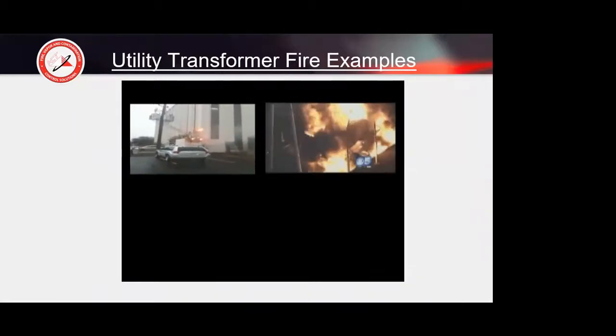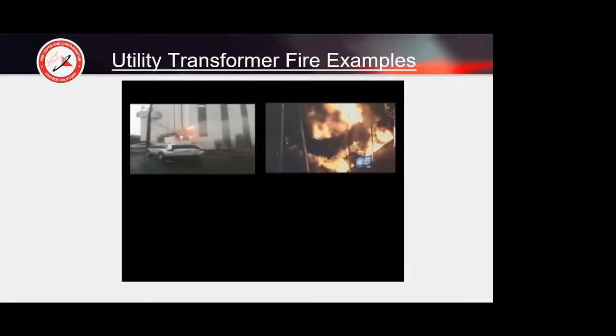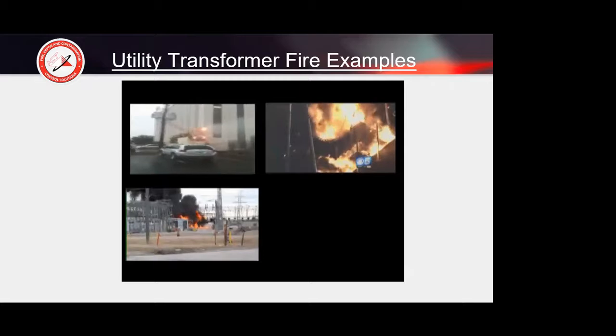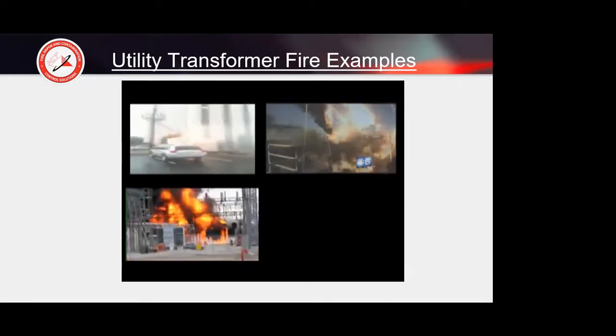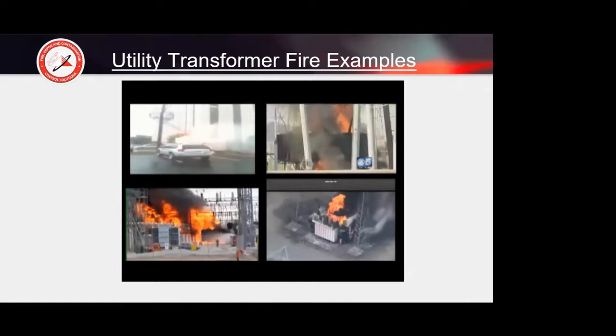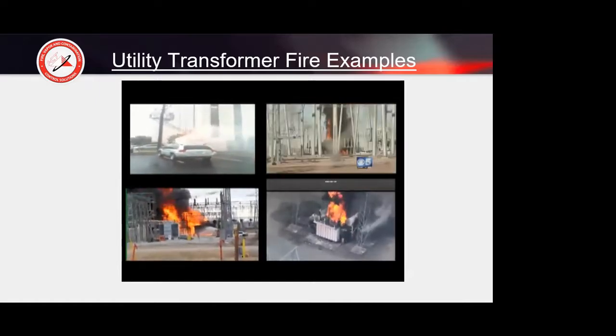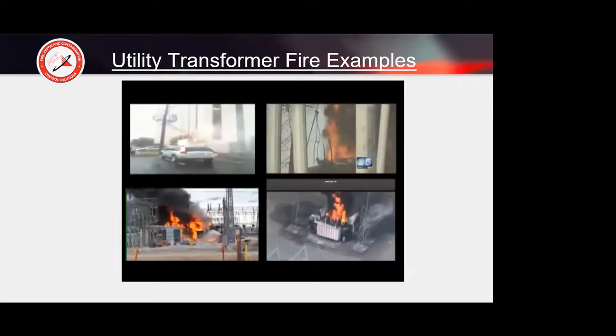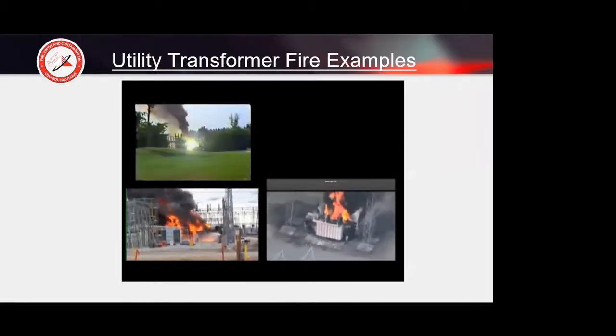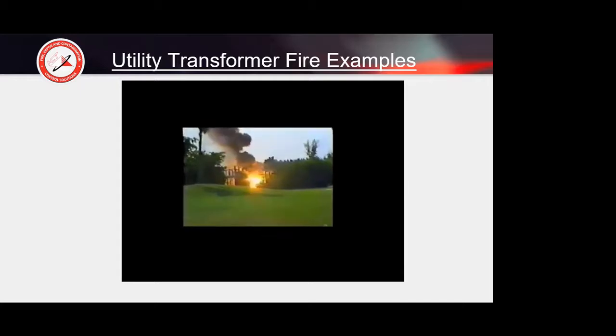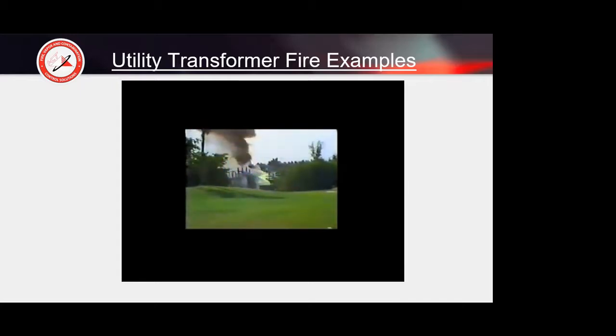So we have a lot of transformers. They're designed for a 25, 30-year shelf life. They've been installed in the 1970s. Means their shelf life is due in, say, 2000. So the incidence of transformer fires is going up greatly, not only in the US, but all over the world. Transformer fire protection is usually designed as plain water. The philosophy is to cool the transformer, keep the fire isolated to one transformer. Don't let it get to the adjacent transformers until the fire department can show up and put the fire out.